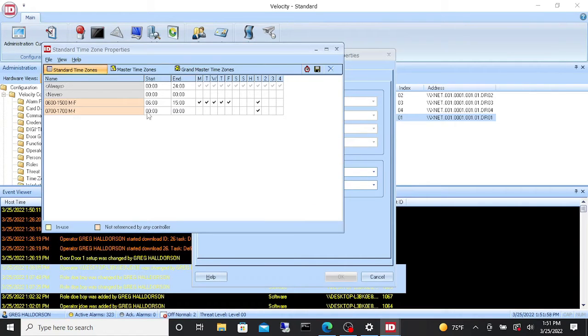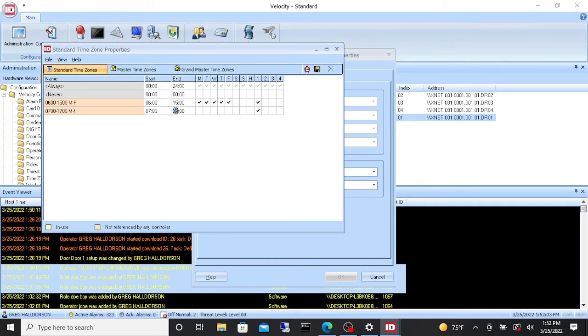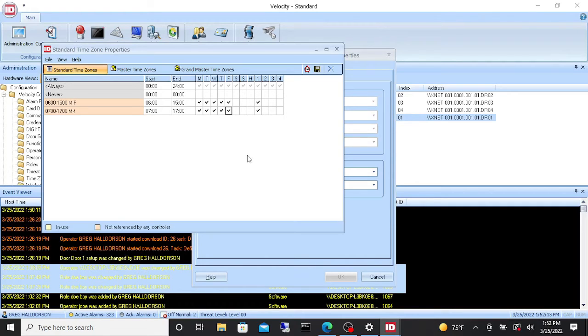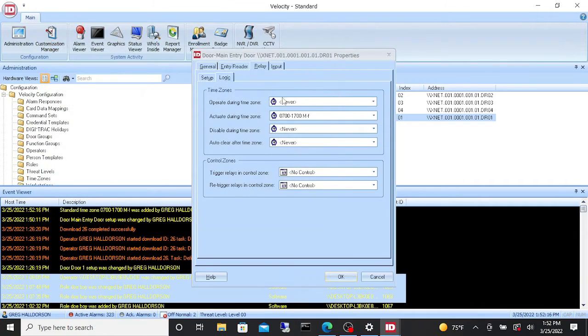That puts it here. We then make that a seven and this a 17, and then we select the days that we want it active on. It's gonna be monday through friday and we'll leave it for holiday schedule one, that way it follows any of the holidays that you set up on schedule one. Now you click save.